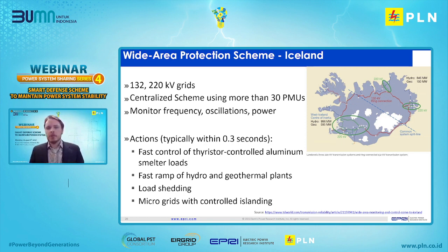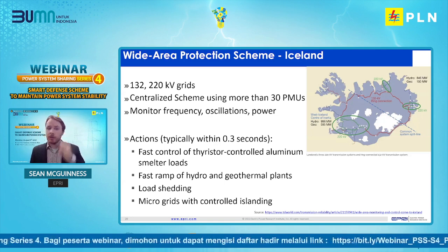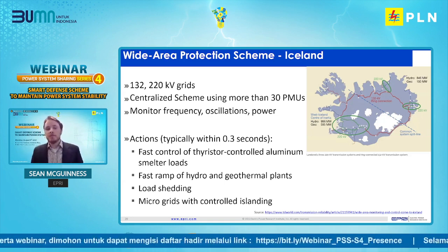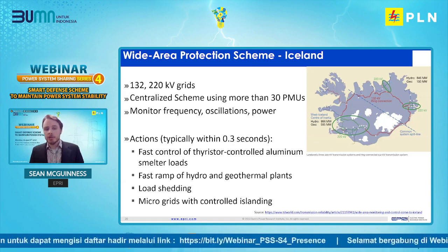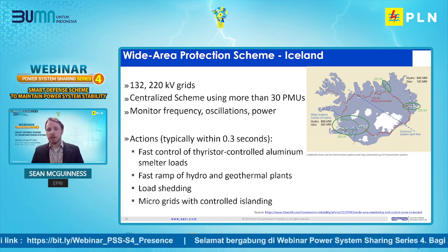As part of this, Landsnet, the power company in Iceland, installed a centralized wide area monitoring and protection scheme using more than 30 PMUs, and it monitors frequency, oscillation, and power flow. And if undamped oscillations or issues are identified or overload conditions, it takes actions typically within 0.3 seconds to activate fast control of thyristor-controlled aluminium smelter plants, to ramp up or down hydro and geothermal plants, to trigger load shedding, and to form microgrids with controlled islanding.